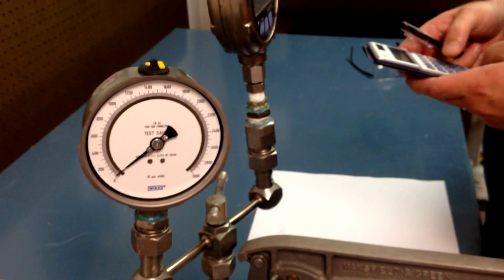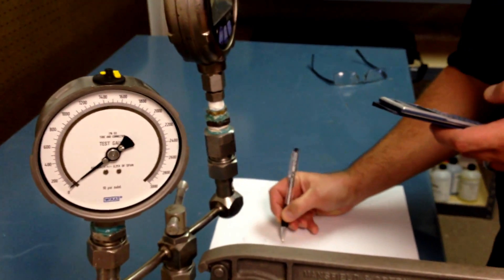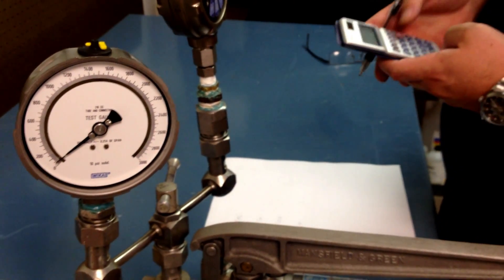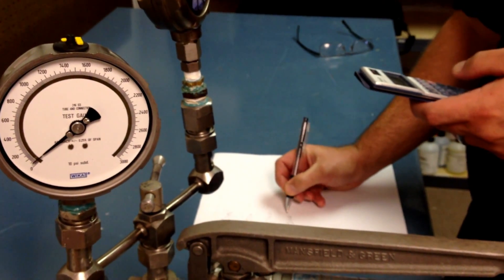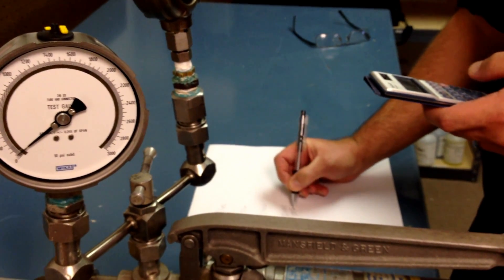So our first point is going to be 750, 1500, 2250 and 3,000. So let's start at the 750 mark, we're going to take this to 750 PSI and compare it against the test gauge.